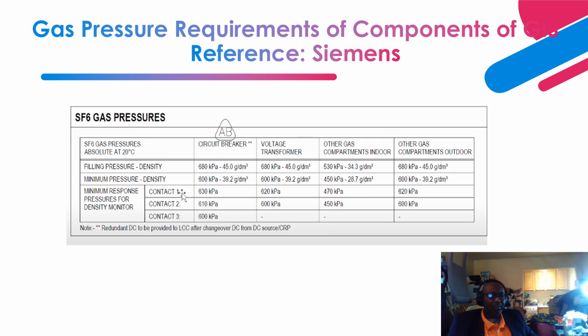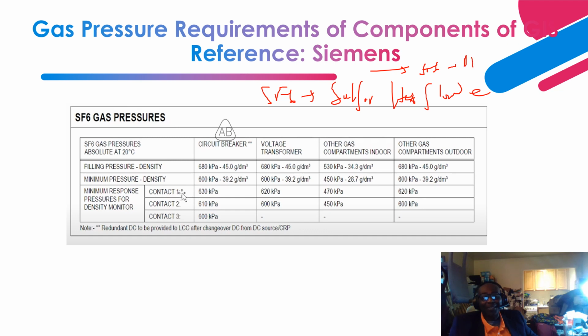Next, let's talk about the SF6 gas, sulfur hexafluoride. This insulating medium, like I indicated, is far better than air. Though it basically creates global warming and political issues, a lot of nations, utilities and different states in the United States are all shifting from SF6 gas as an insulating medium to alternative, SF6-free gas. SF6 gas has been good, and it basically has high dielectric properties, 3 to 4 times that of air.